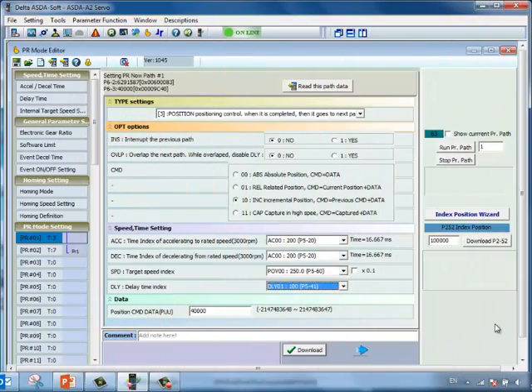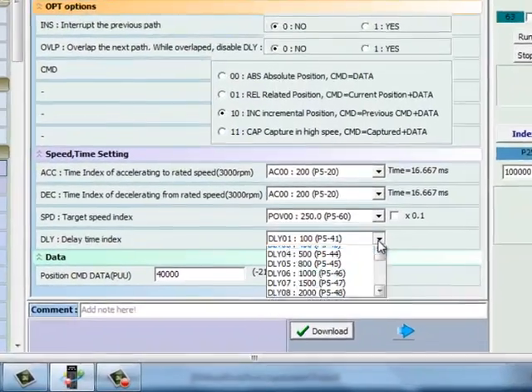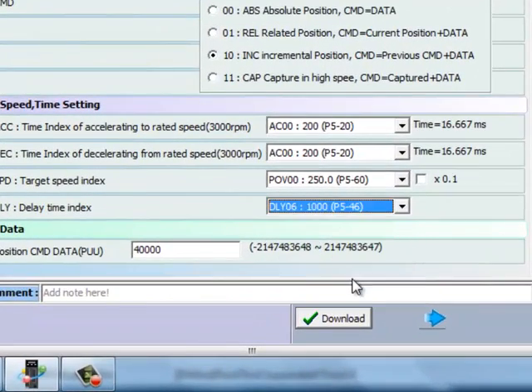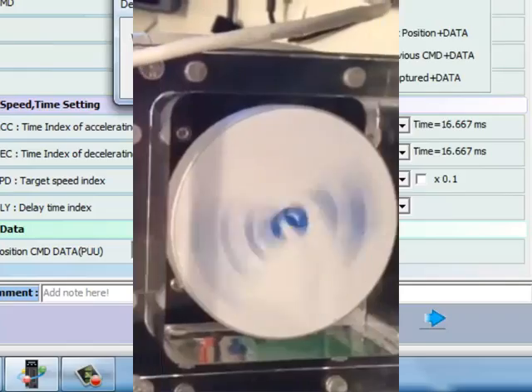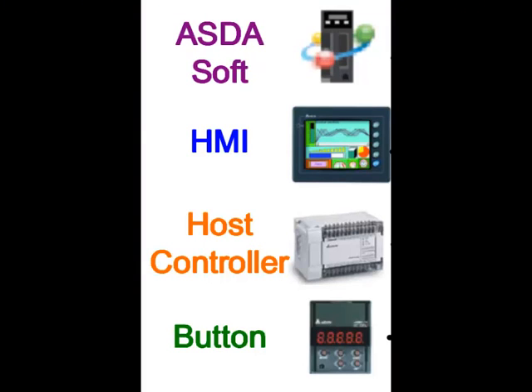To change the amount of time between indexing, just change the delay time in the PR mode editor, and we can see that the change has been applied. All of these parameters can be changed on the fly without the need for a PC using a PLC or an HMI for communications.